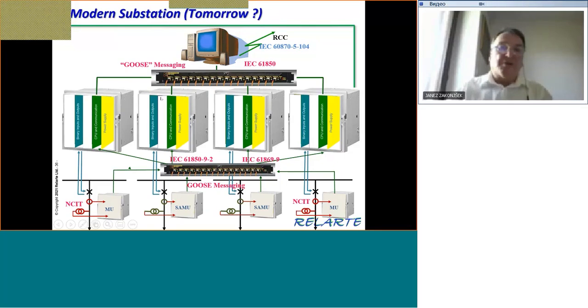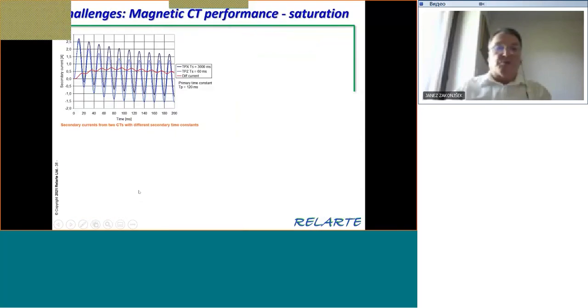You see in these boxes there are no more analog input cards and so on, but signals come from standalone merging units located away from relay protection, connected to conventional current and voltage transformers, or if using non-conventional instrument transformers, they go directly to the merging unit, or already have it included. All these sampled values and signals go directly to certain parts of the substation and communication.